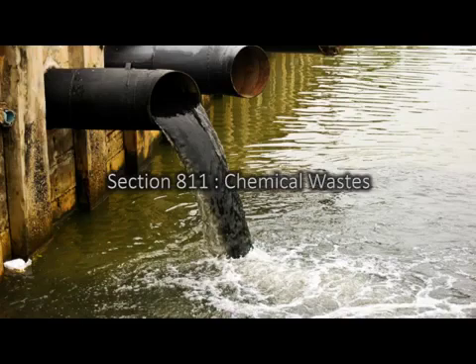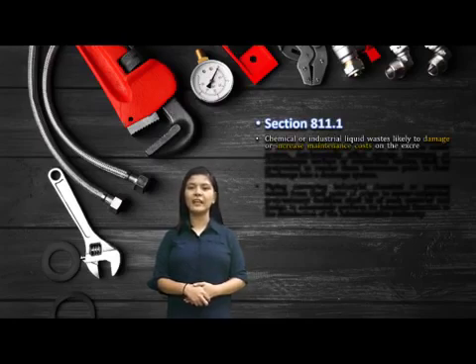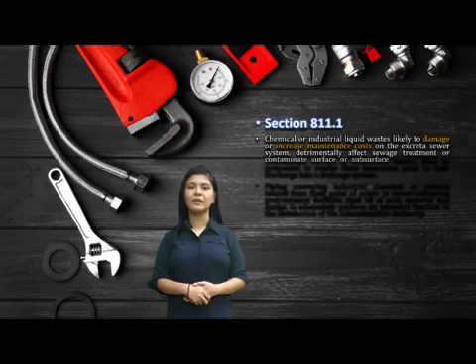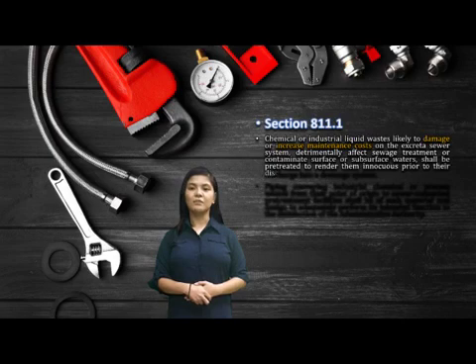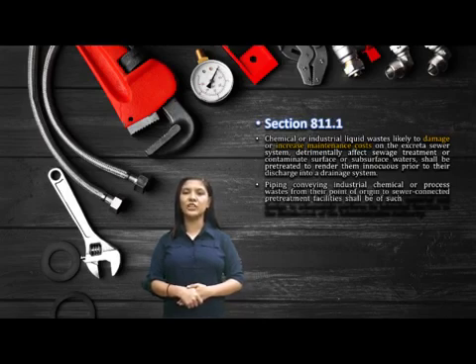Let's proceed to Section 811, Chemical Waste. This section is very important; it has eight subsections. As we know, chemicals have more hazardous characteristics and need to be separated and disposed of properly. Section 811.1: Chemical or industrial liquid waste likely to damage or increase maintenance costs, or that may affect sewage treatment, or contaminate surface or subsurface water, shall be treated to render them innocuous prior to their discharge into the drainage system.